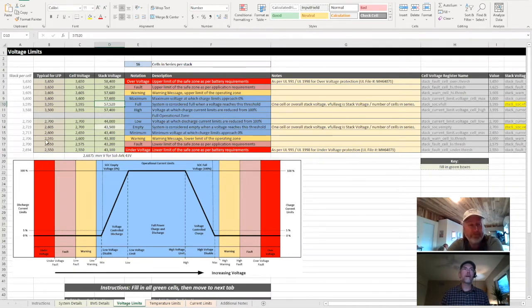Sure, so these are the settings for the BMS. Essentially we're saying if the stack gets to 57.52 volts, we're considering that completely full. We don't need to go any higher than that. It can safely go a little bit higher if something happens, but the contactors won't open until a bit higher than that.